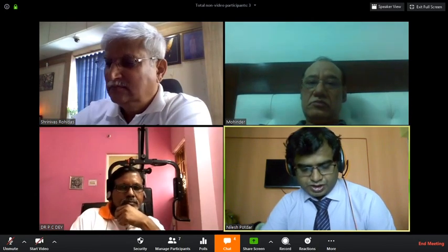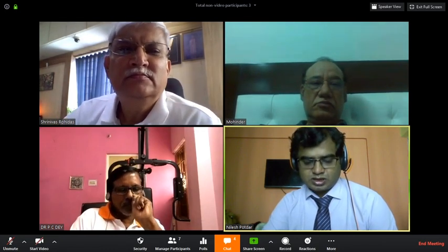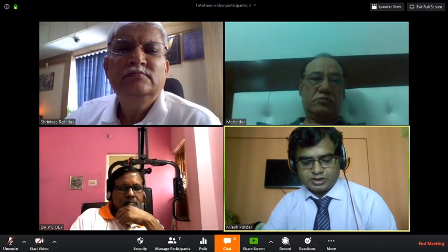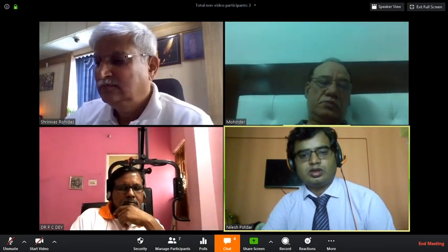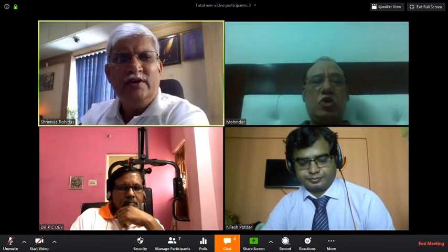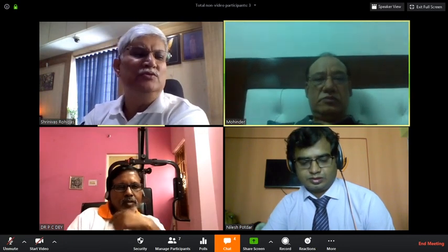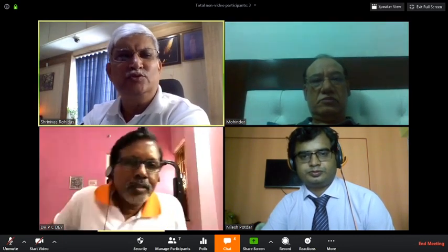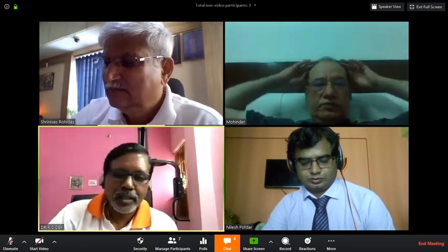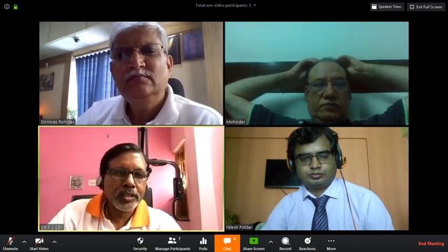This is the next question from Sandeep Saraf, Visakhapatnam. He is asking, is the Storz system working channel port compatible with any other company 4 mm 0 degree scope? Yes, any scope you can use. It is a universal scope. This scope can be used in sinoscopy and arthroscopy. Another company's scope can be fitted with an adapter, but if you use Smith and Nephew or some other company's telescope, it will not fit.